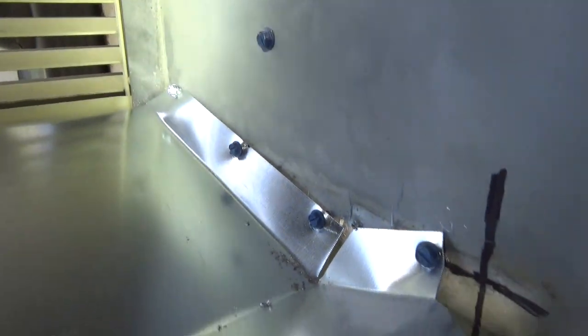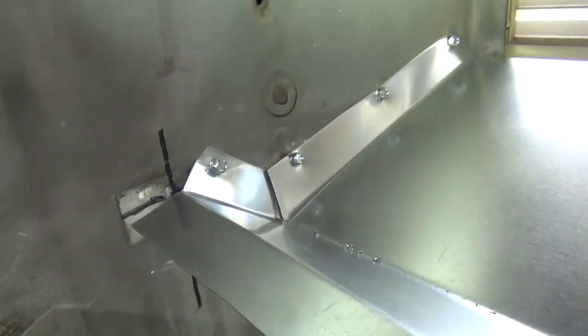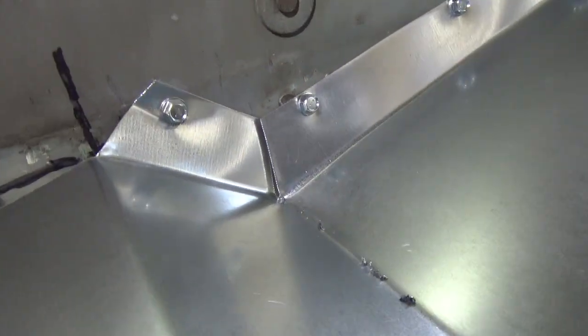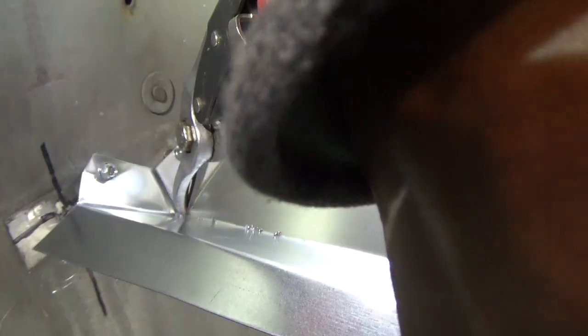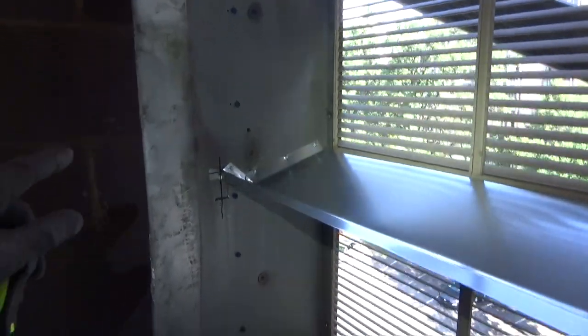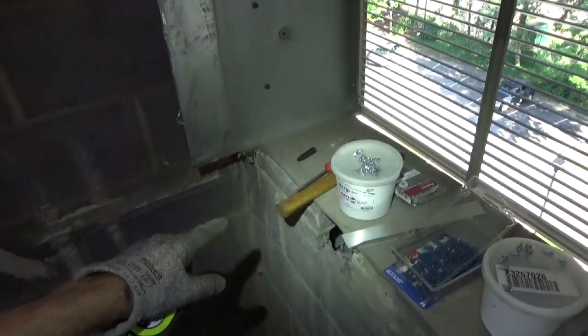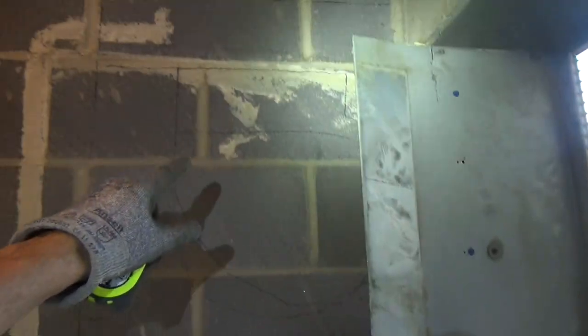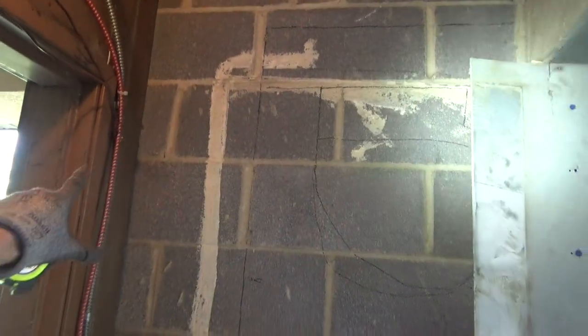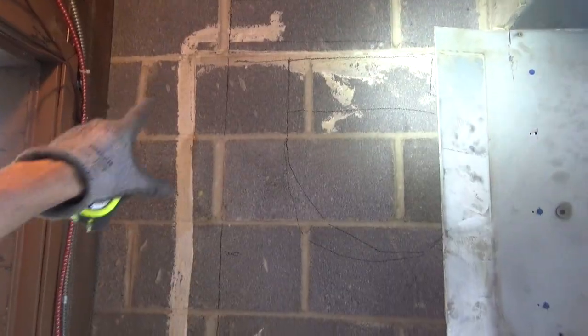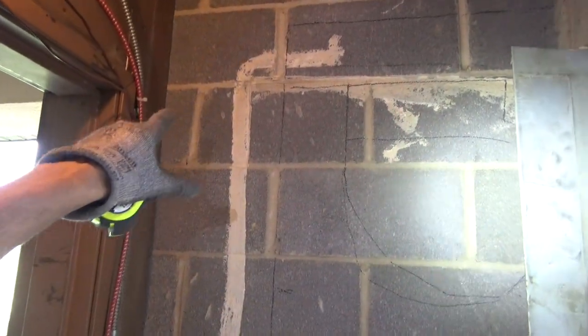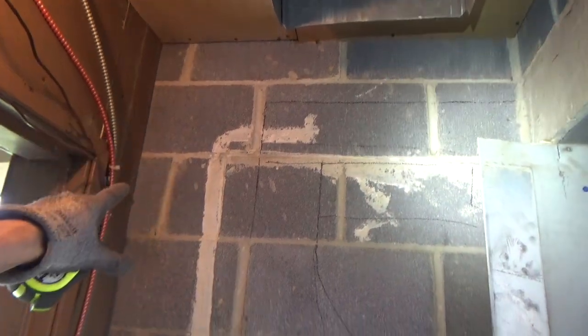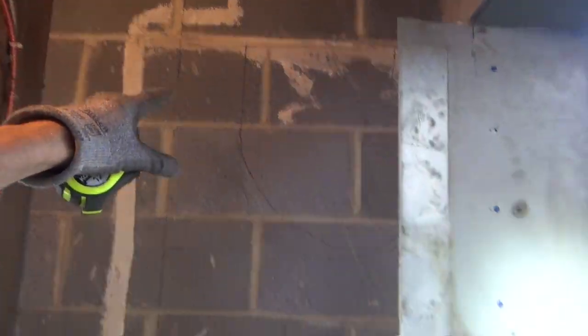I had to use Tapcons on this side, just right up on the cement. So now you want to make sure you got a drain. It's not going to clog, and I just whack it. So I'm going to alter this one on this video. I'm going to drop down 2 more inches because I drew the fan right there, and it's just not going to squeeze. If that fan's ever got to get pulled, it's not going to fit through that hole. Plus the evaporator goes way up high. I'm going to go down 2 more inches.